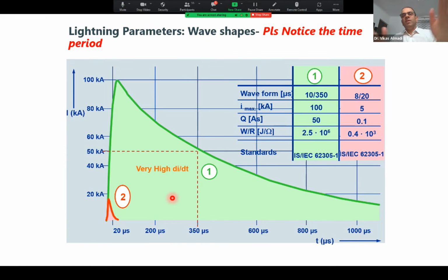That is why, when you are making an earthing system, you make a grid. If you don't make the grid, there will be an effect of L di/dt too, apart from other things. All this is not being drawn by me. These are all mentioned in IEC standards, which are adopted in IS standards. Many of us know about the 2309 standard, which has been abolished, and the new standard is IEC 62305, since 2016, not new.